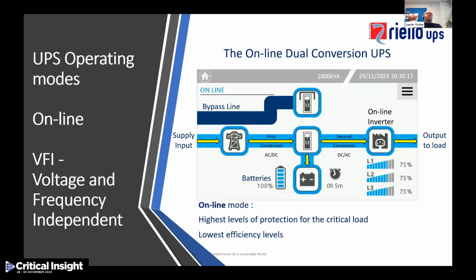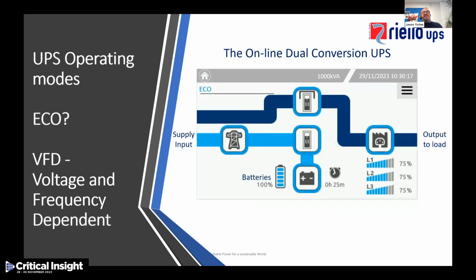Now, to address this, many UPS manufacturers, including ourselves, can operate the online dual conversion UPS system in different modes of operation. One of these modes is eco mode. Eco mode is so called because it provides a high level of efficiency, and the reason is that the load is being powered directly through the bypass line.